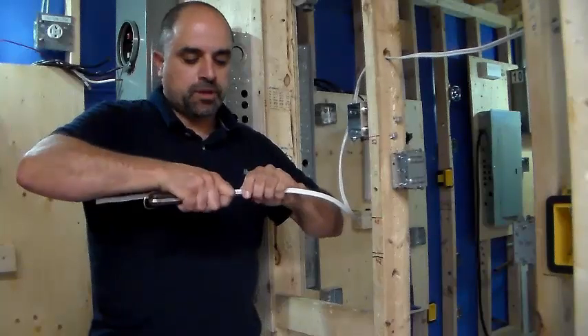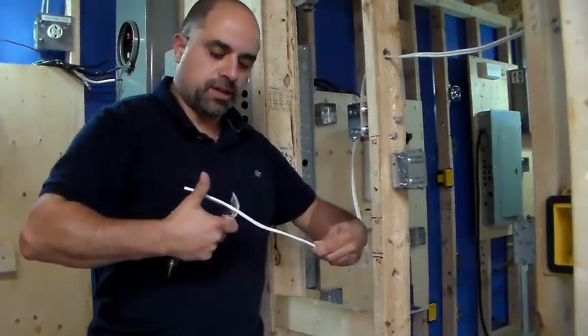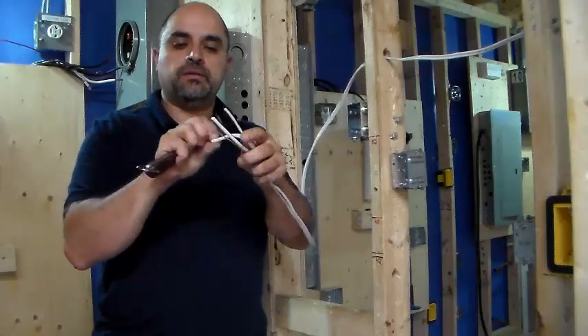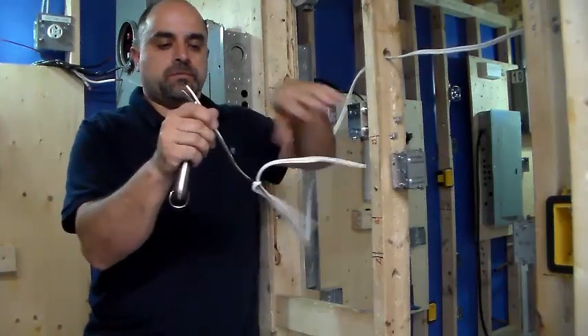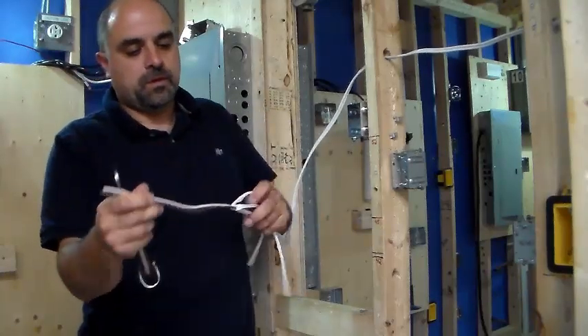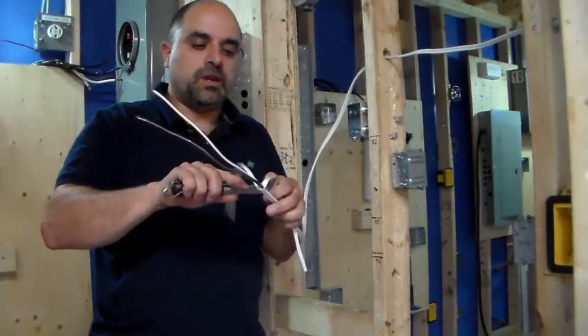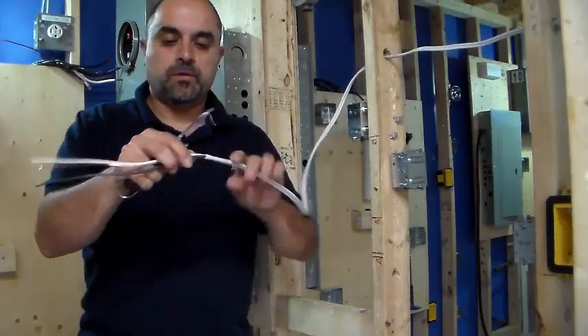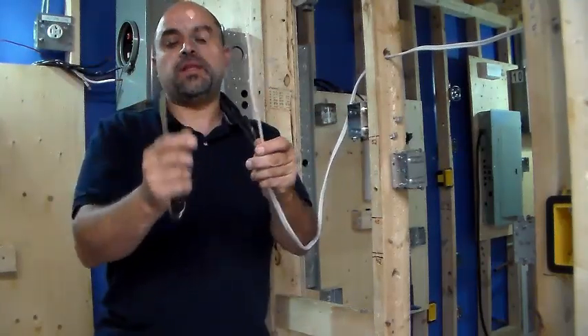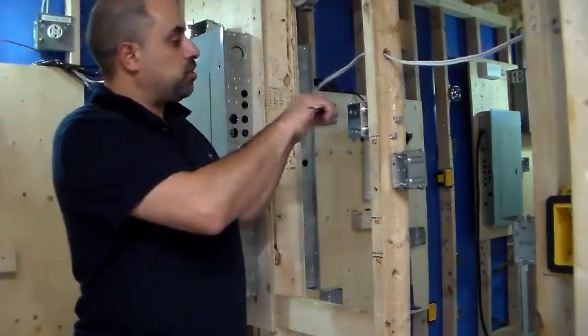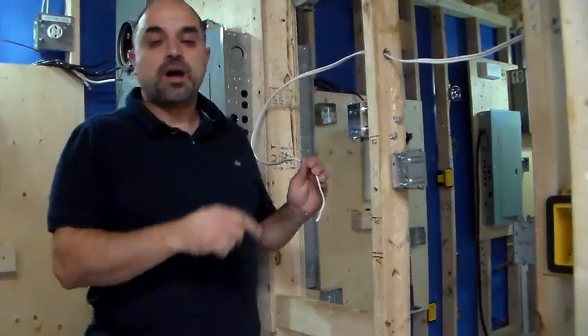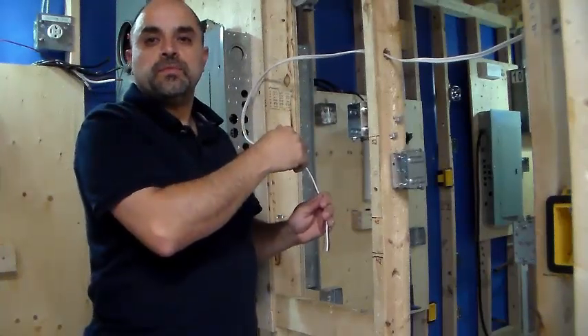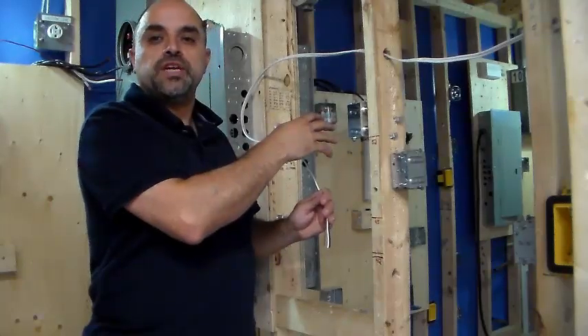So you take your cable and you take your knife. If you're using a 14-2, you can run it down the middle to strip the cable along the copper. And take the outer sheath. Cut it off but be careful not to nick the wires. Take the outer sheath off. So that you have the black and white and ground left over. And then you're going to install it into the box. The top of each of the boxes has little holes that you can take out. So you can put it into the box and then make your connections. We'll move in closer so you can see exactly how that's done.